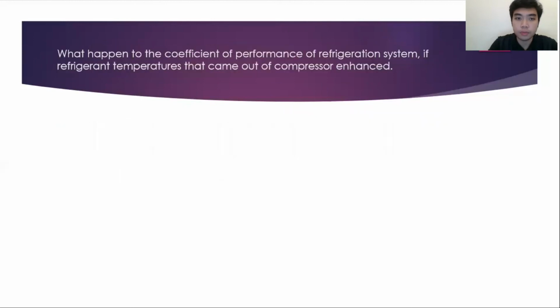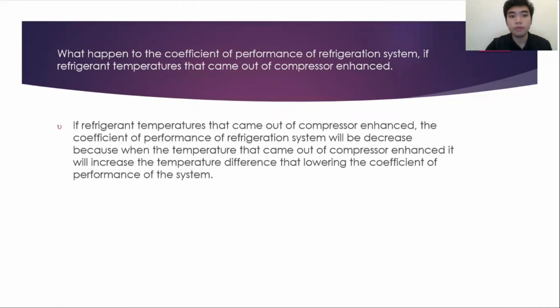Next discussion is what happened to the coefficient of performance of refrigerant system if refrigerant temperature that came out of compressor enhanced. If the refrigerant temperature that came out of compressor enhanced, the coefficient of performance of the refrigerant system will decrease, because when the temperature that came out of compressor enhanced, it will increase the temperature difference, lowering the coefficient of performance of the system.